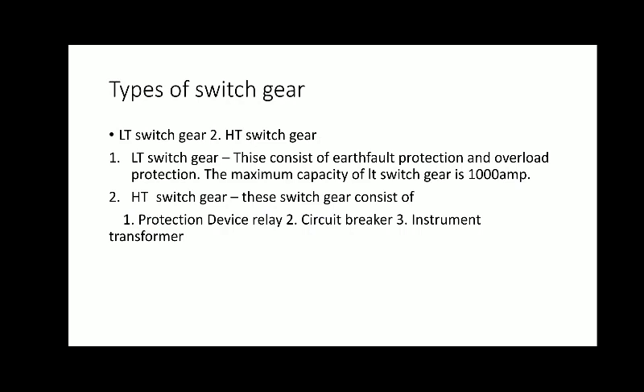First one, there is a LT switch gear and HT switch gear. So LT, low tension switch gear, HT, high tension switch gear. In LT switch gear, these consist of earth fault protection and overcurrent protection. The maximum capacity of LT switch gear is 1000 ampere. Capacity of this switch gear is selected according to the load requirement.